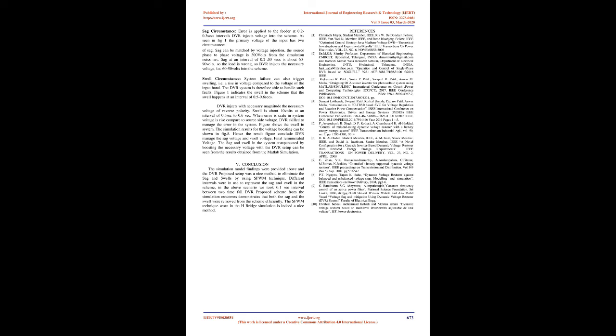Swell condition: a system fault can also trigger a swell, i.e. a rise in voltage compared to the input voltage. The DVR system is therefore able to handle such faults. Figure 1 indicates the swell in the system, which happens at an interval of 0.5 to 0.6 seconds. The DVR injects the necessary voltage with the necessary magnitude and reverse polarity. The swell is about 10 volts at an interval of 0.5 to 0.6 seconds. When a fault is created in the system, the voltage rises compared to the source side voltage. The DVR is able to manage the fault in the system. The figure shows the swell in the system.